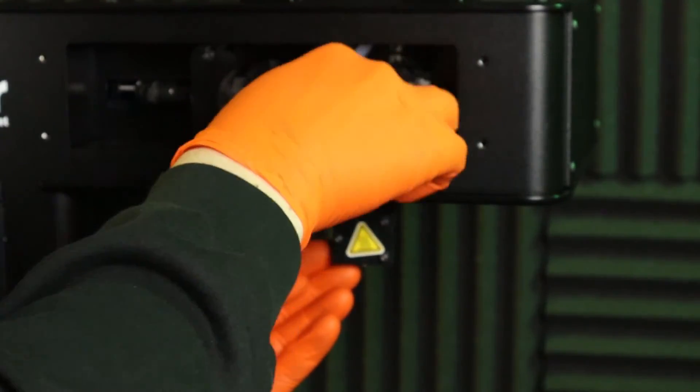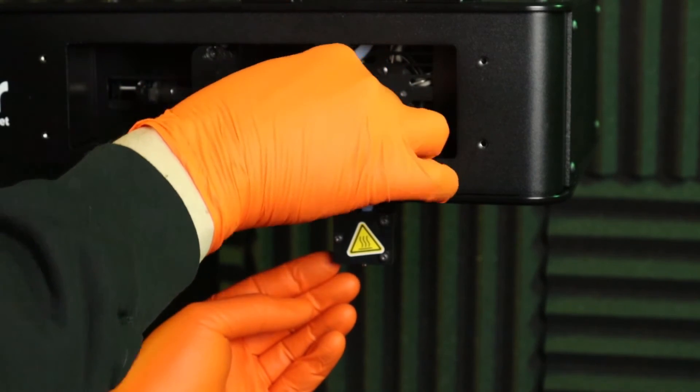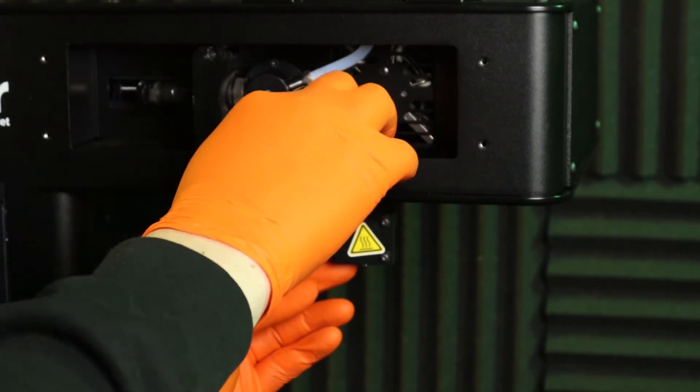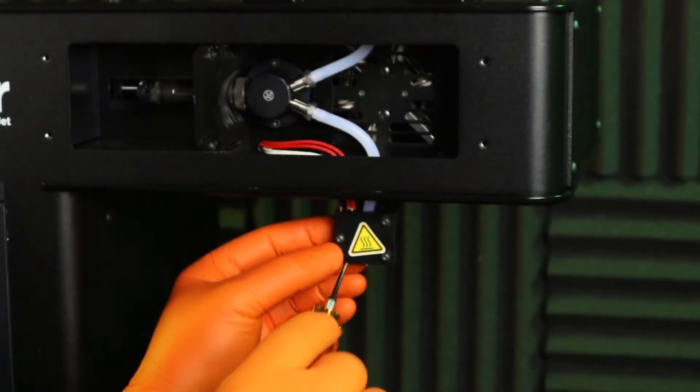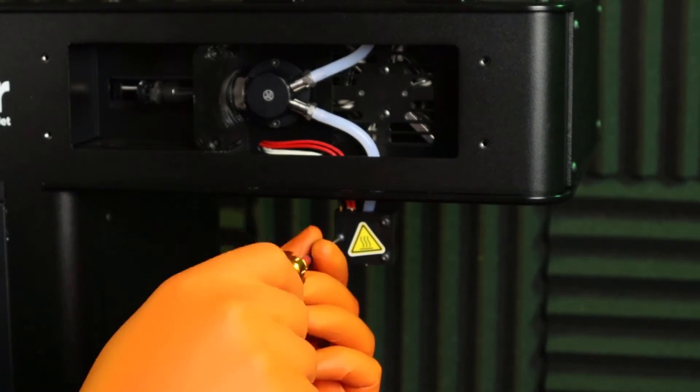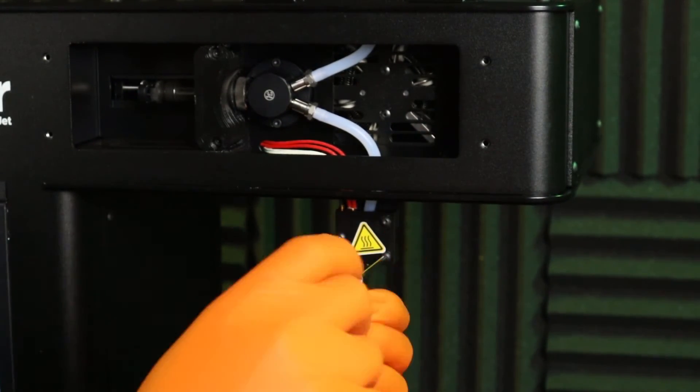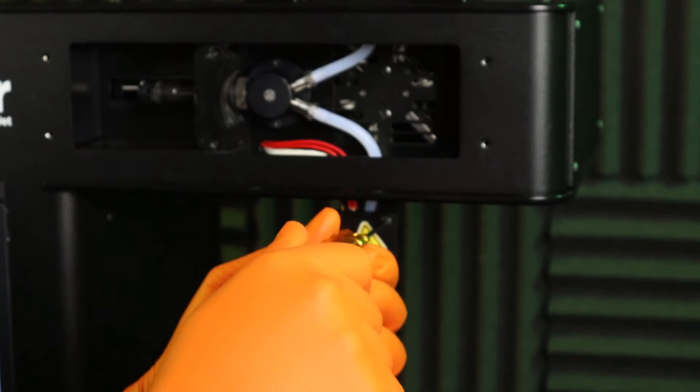If needed, you can adjust the placement of the heater and thermistor wires by pulling or pushing from within the pump chamber. Insert the final screw and ensure all three are hand tight until you feel resistance. Do not over tighten.